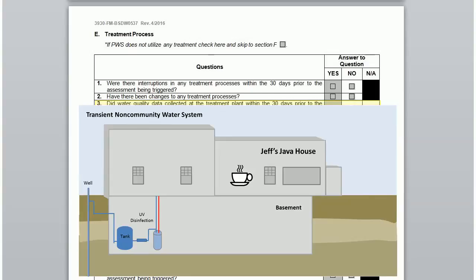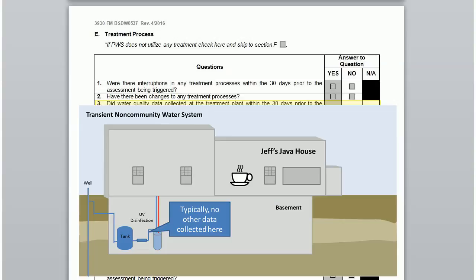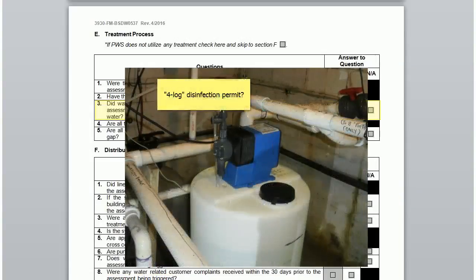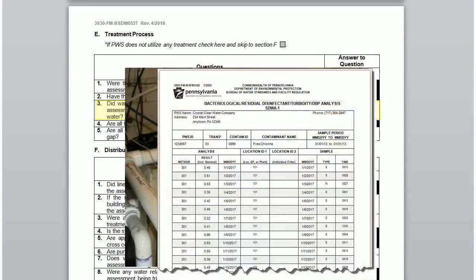For non-community systems watching this tutorial, you probably don't have any additional data that you collect just after your treatment equipment — you would check NA for this. But if you were previously required to install 4-log disinfection, then you'll have entry point chlorine data. In this case, check the trend of your daily chlorine data. You should already have been aware of any time it dipped below your permitted level.